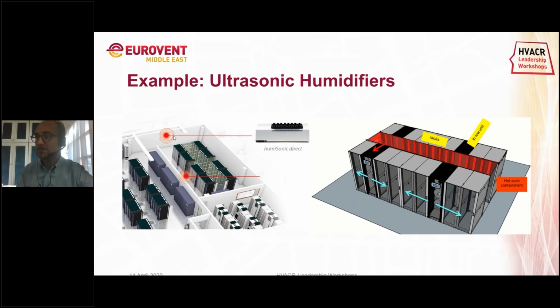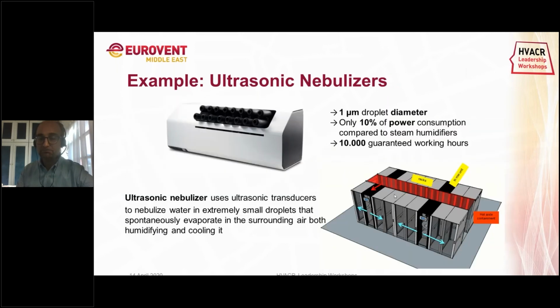But for example, in this case, imagine you have hot aisle containment and room. These kinds of units can modulate, they create 1 micron droplets of water, and using very low power, less than 10% of power consumption compared to isothermal humidifiers that have to boil water, they can work for a very long time. This type of humidifier should include water treatment to avoid having any type of mineral and dust in the data center. These nebulizers in the end can properly modulate the amount of humidity, and they use a small amount of energy.